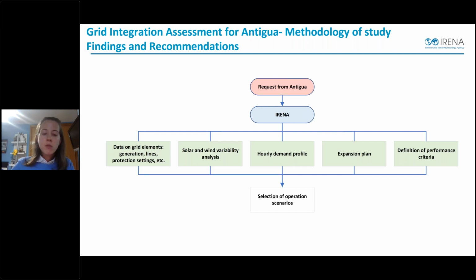After receiving the request from Antigua and the subsequent affirmative response from IRENA, it started the data collection process. As seen in the graph, data on grid elements such as generation lines, solar and wind variability, hourly demand profiles, expansion plans, and the definition of performance criteria are needed in order to select the operation scenarios based on PV and wind penetration. This is a snapshot of all possible situations along the year that represents the key operation scenarios.